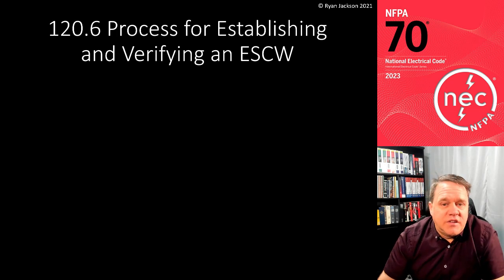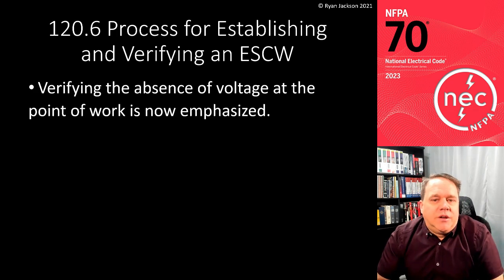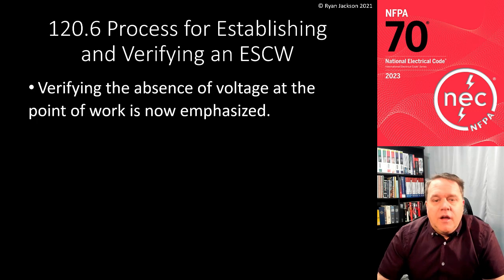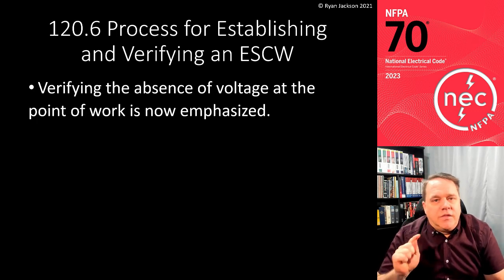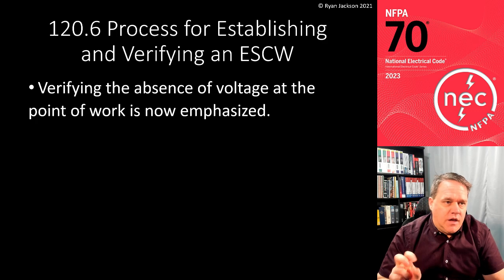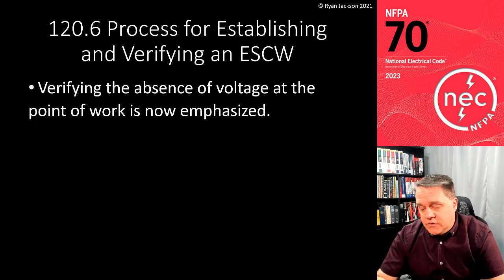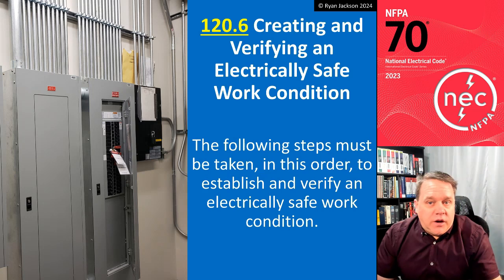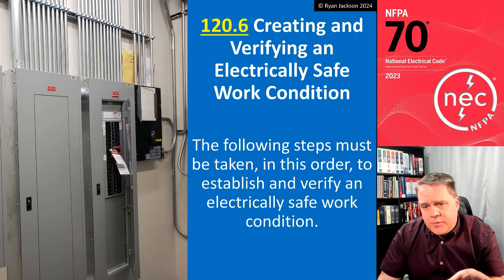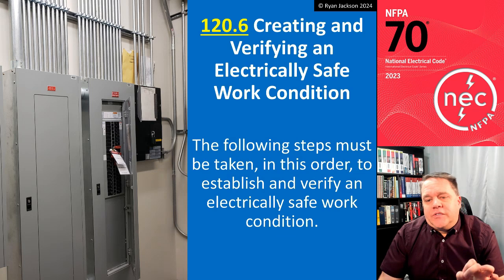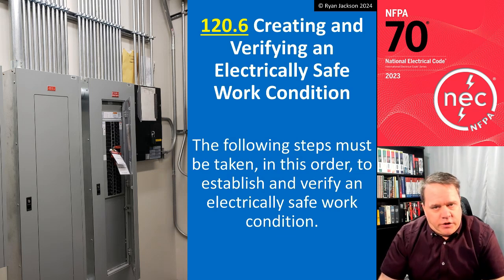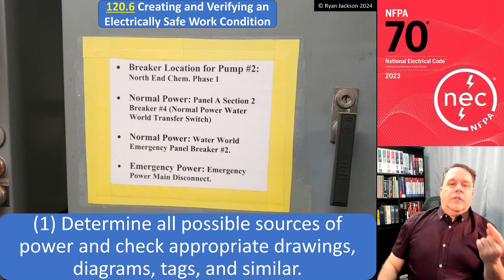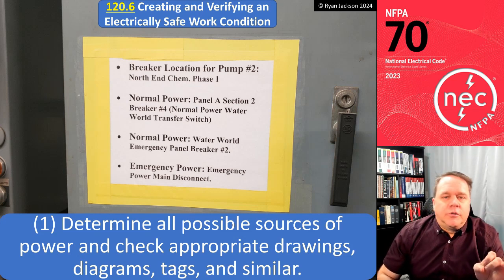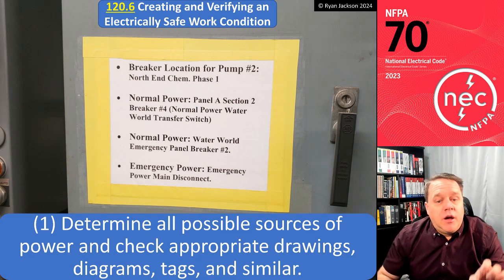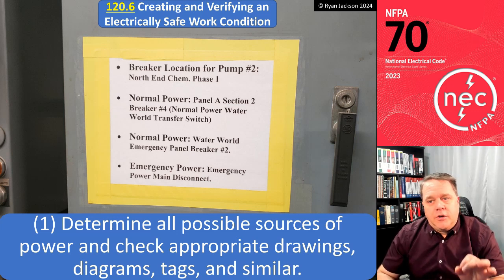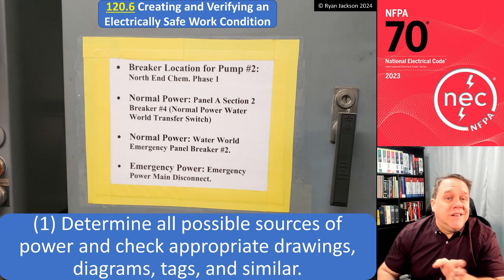All right, 120.6, the process for establishing and verifying an electrically safe work condition. Verifying the absence of voltage at the point of work is now emphasized. I think this is a really good change. This is something that's quite important. 120.6, the following steps must be taken in this order to establish and verify an electrically safe work condition. Now, as we've said before, the first step, determine all possible sources of power and check appropriate drawings, diagrams, tags, and similar. So we need to figure out exactly what needs to be shut off.